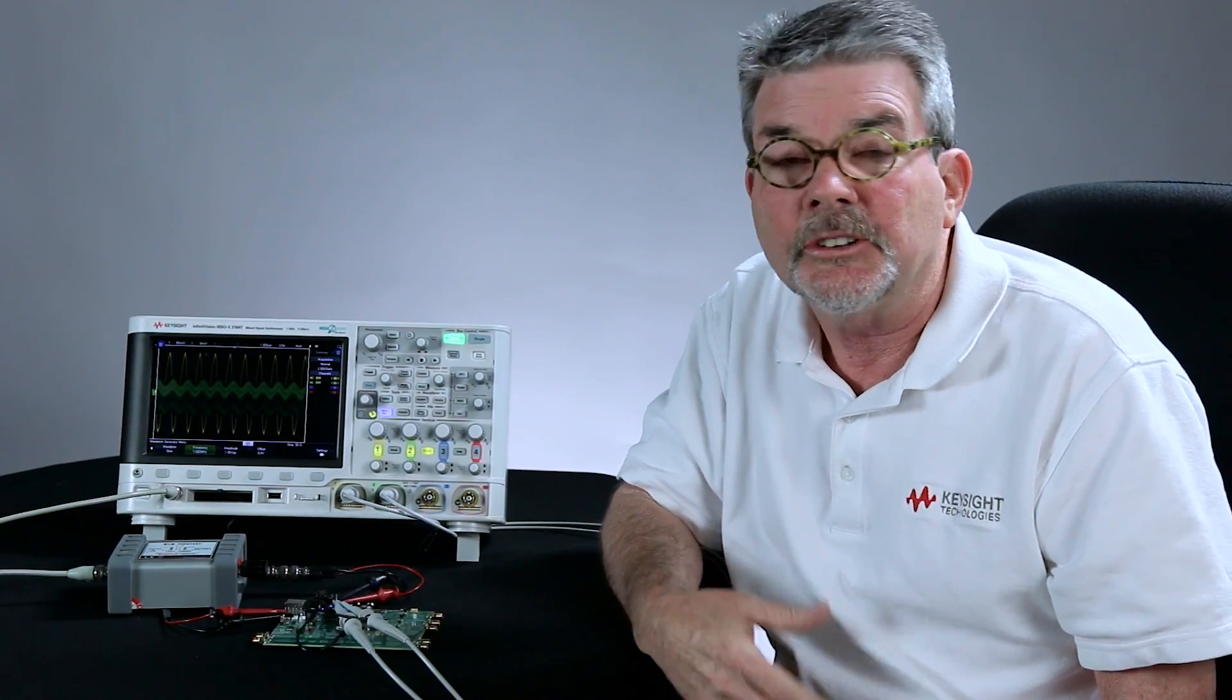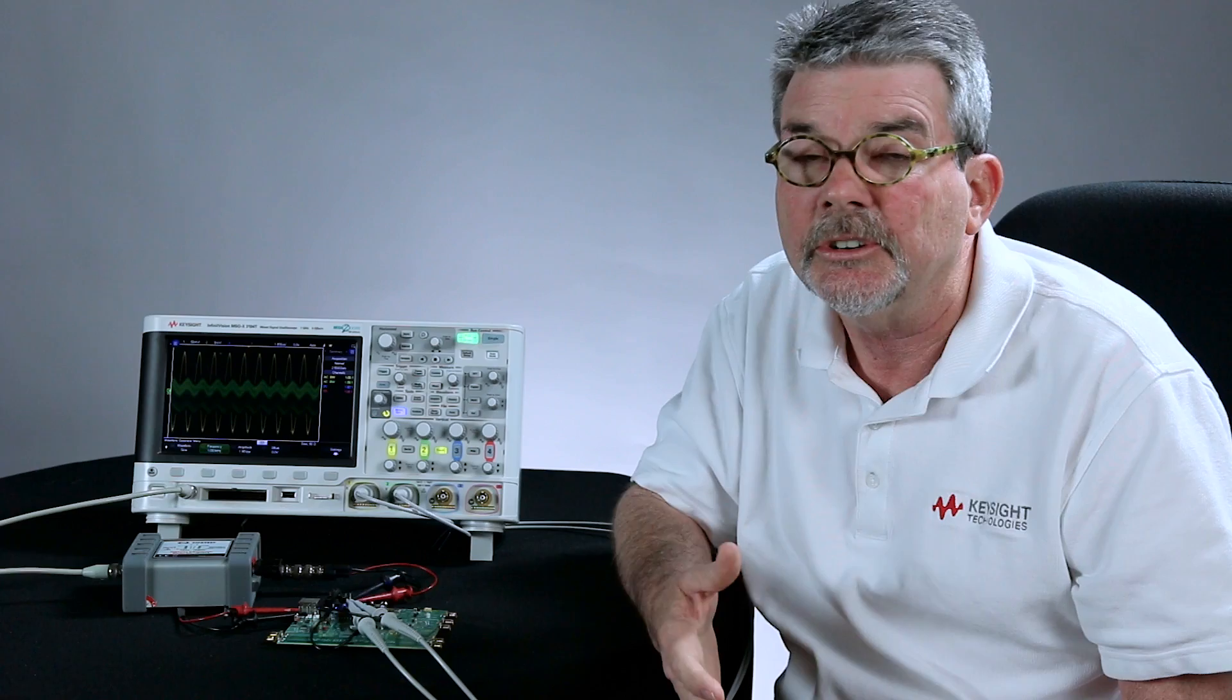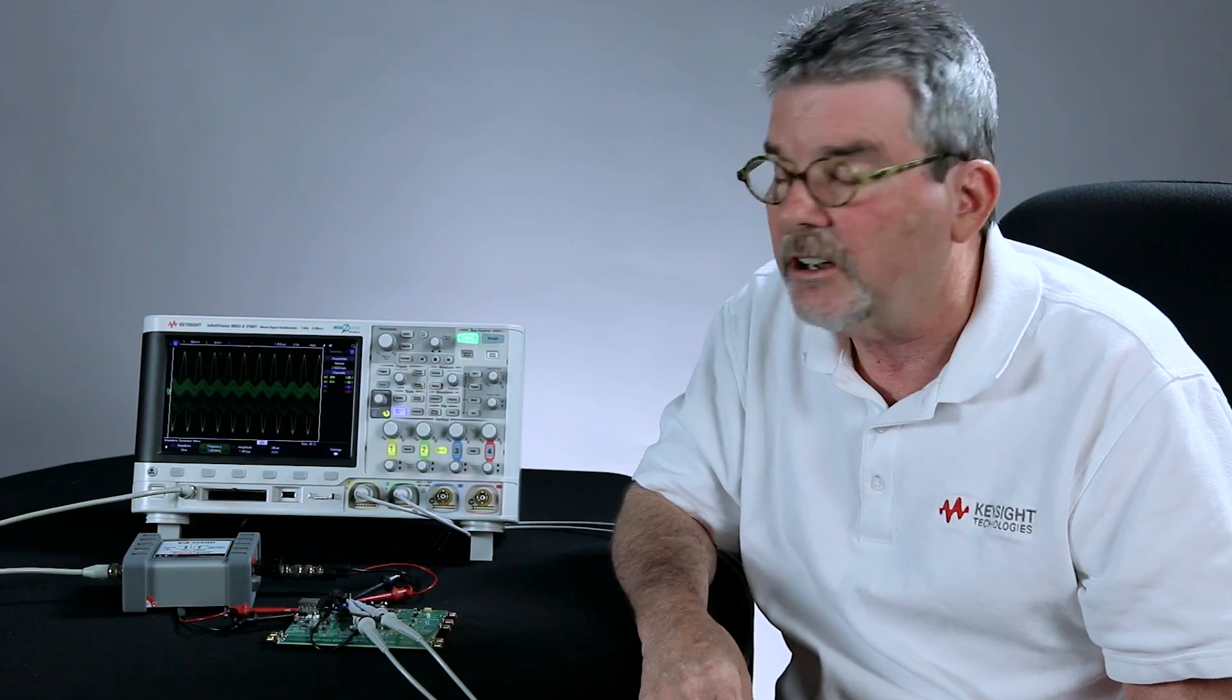Now a control loop response measurement is basically a Bode gain and phase measurement. You typically use either a network analyzer or a frequency response analyzer to perform this type of measurement. It's a very critical measurement to characterize the stability of your power supplies.